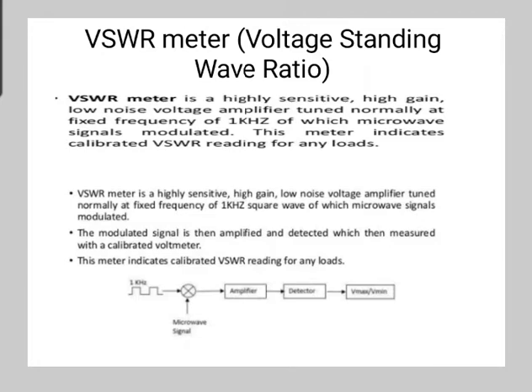So it is a sensitive voltage amplifier normally tuned at a frequency of 1 kHz. The modulation of the microwave signal takes place at this frequency. The VSWR meter has high gain, high Q and low noise. The microwave detector sends the signal. This detected signal is applied as an input to the VSWR meter. A square law calibrated voltmeter is used to measure the output of the amplifier, and this measured output directly provides the VSWR reading as Vmax by Vmin. Initially, for the Vmax input, the meter is fixed to unity VSWR.